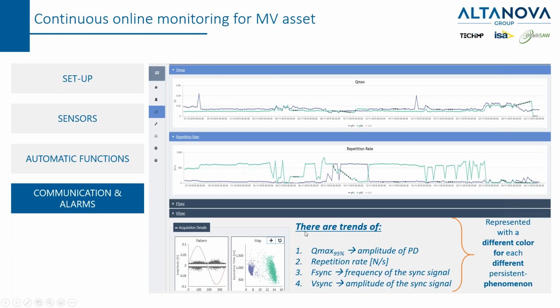The trends are basically counting of Qmax, repetition rate, synchronism frequency, and synchronism amplitude. These are different colors for each different persistent phenomena. The unit can acquire up to 4 different persistent phenomena, separate them in different trends, and then the operator, this is for more skilled operators, can perform the analysis and reach some conclusions in terms of assessment on the asset.